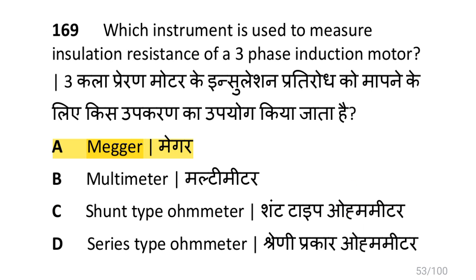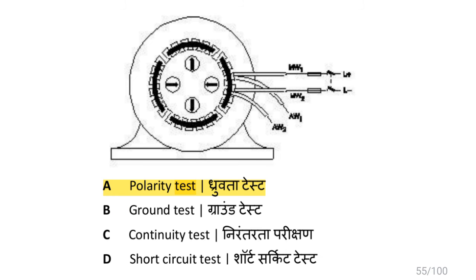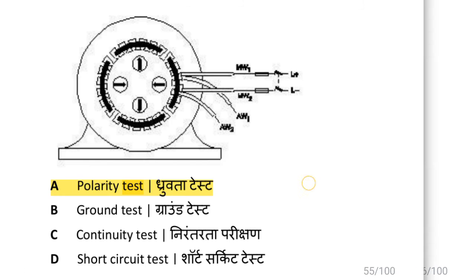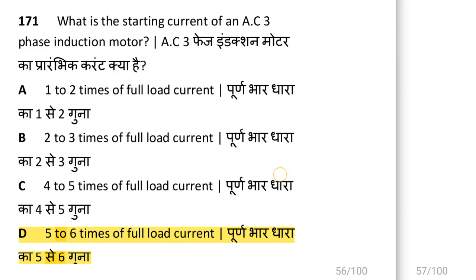The instrument used to measure insulation resistance of a three phase induction motor is a megger. The test illustrated in the winding is the polarity test. The starting current of an AC three phase induction motor is five to six times the full load current.